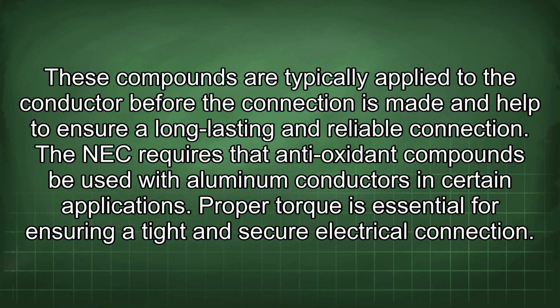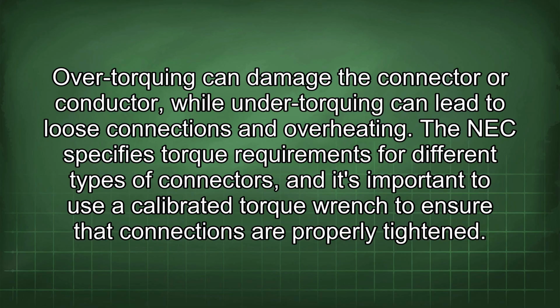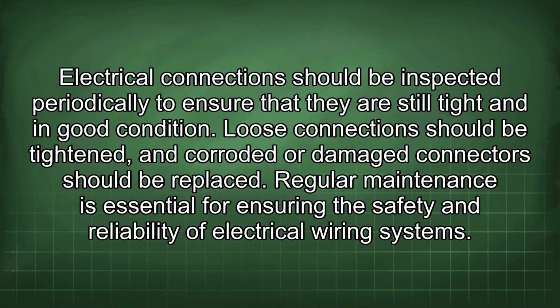Proper torque is essential for ensuring a tight and secure electrical connection. Over-torquing can damage the connector or conductor, while under-torquing can lead to loose connections and overheating. The NEC specifies torque requirements for different types of connectors, and it's important to use a calibrated torque wrench to ensure that connections are properly tightened. Electrical connections should be inspected periodically to ensure that they are still tight and in good condition. Loose connections should be tightened, and corroded or damaged connectors should be replaced. Regular maintenance is essential for ensuring the safety and reliability of electrical wiring systems.